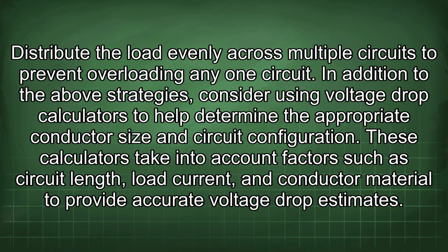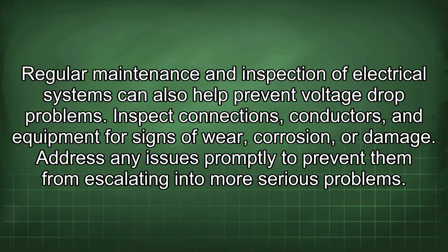In addition to the above strategies, consider using voltage drop calculators to help determine the appropriate conductor size and circuit configuration. These calculators take into account factors such as circuit length, load current, and conductor material to provide accurate voltage drop estimates. Regular maintenance and inspection of electrical systems can also help prevent voltage drop problems. Inspect connections, conductors, and equipment for signs of wear, corrosion, or damage. Address any issues promptly to prevent them from escalating into more serious problems.